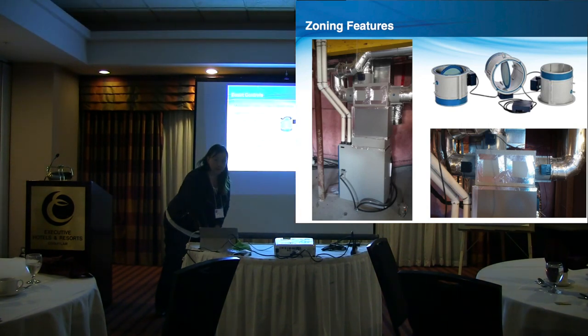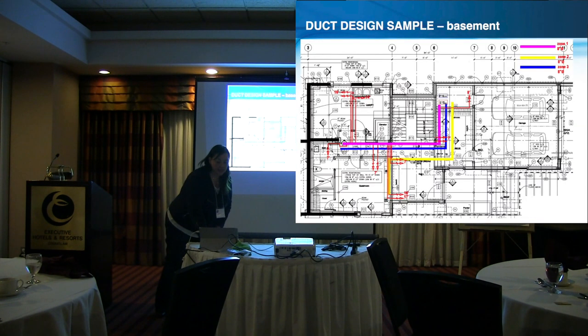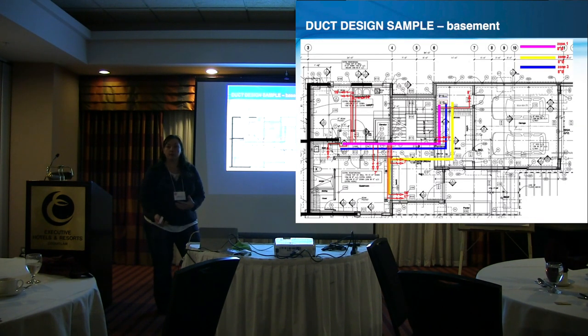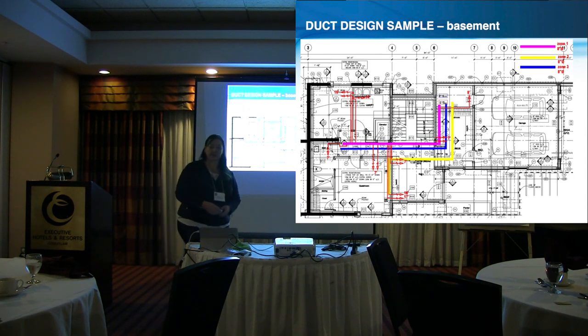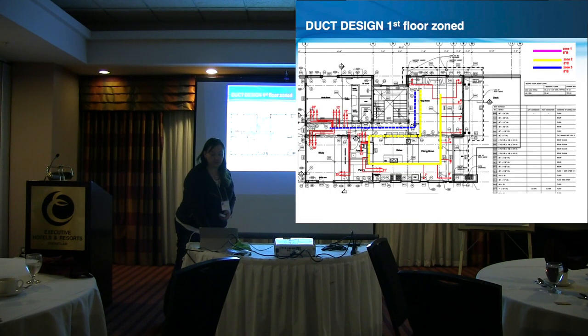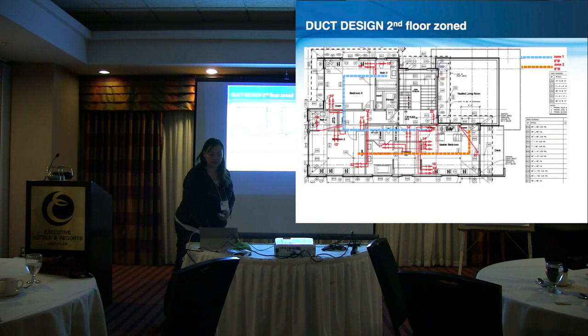And it's all about static pressure. We want to keep everything at the right static pressure all the way through so the zones don't fight each other. And then, remember, when we do our smart duct design, it's basically zone ready because we're designing per floor. So sometimes even a structural beam will be zoned by floor and zoned naturally with the smart duct system. So this takes it even a step further, with zoning to drive comfort through specific zones.